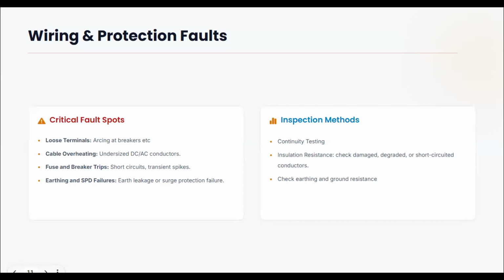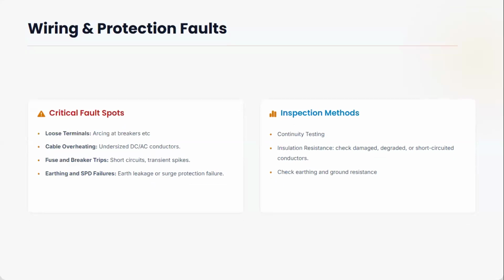So, cable overheating. This comes from partial contacts or at the connection terminals, or when cables are undersized. Maybe there is now an overload on the cable, or the cable was originally undersized. If the cable is within the normal standard of current capability, then there's no reason for it to heat up, unless it's a mixture of a kind of alloy that makes it poor quality. If not, then it works properly.